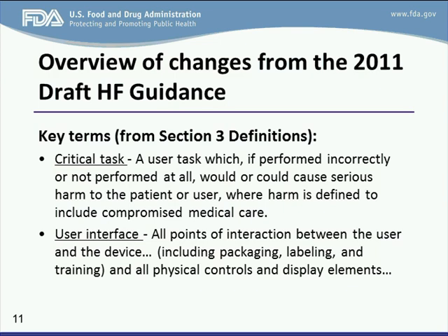And then user interface. When we say user interface, we're referring to all points of interaction between the user and the device or the product. That could be packaging, labeling, training, the graphical user interface, any controls. If the device is portable, it could be the way that it's handled, the handles on it. All of those items we're referring to when we're talking about user interface.